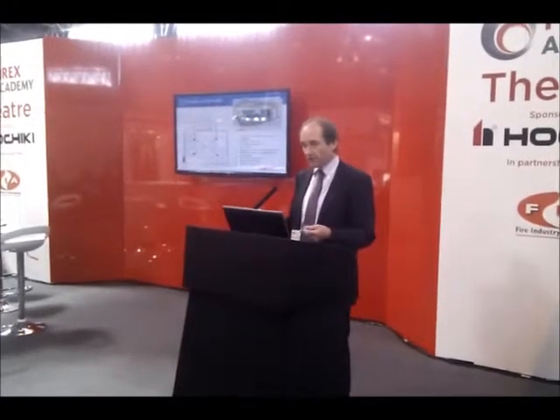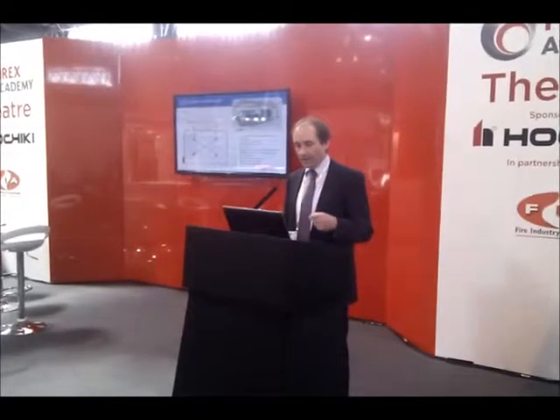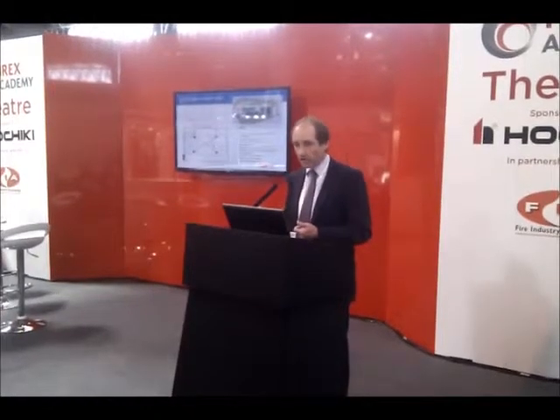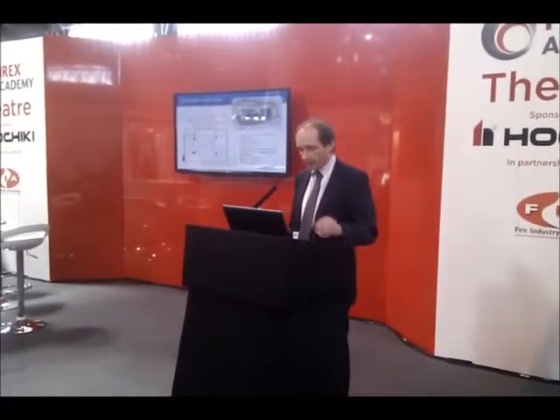The schematic shows the cross-zoning of the system. Generally, the detectors — whilst they may be of the same type — are spaced apart from each other so that you don't get two detectors on the same zone going into alarm without triggering the coincidence operation. They are configured in such a way that you achieve a true coincidence and double-knock situation.